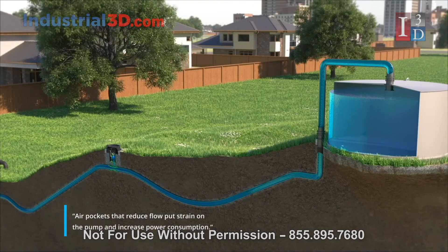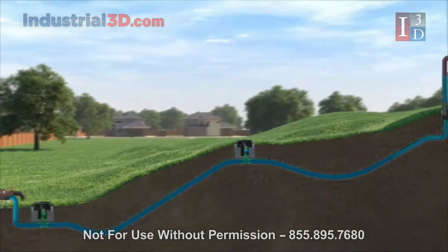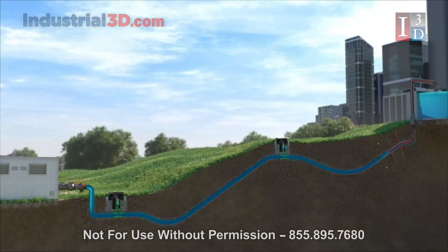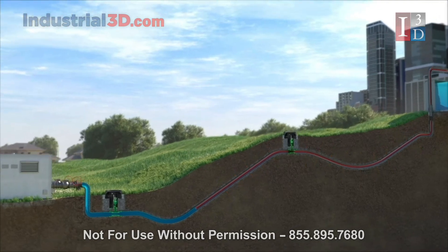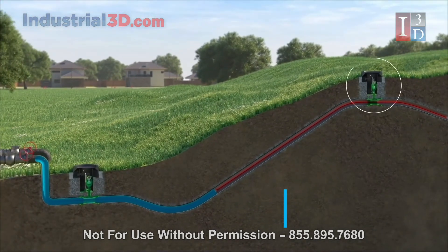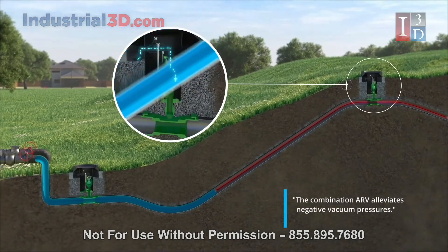Once the pump cycle is complete, the media begins to flow back down the pipeline. A vacuum situation is occurring because no air is being introduced back into the pipeline. The valve allows air to be introduced back into the line to prevent avoidable catastrophic situations.